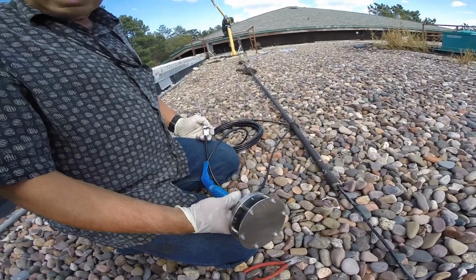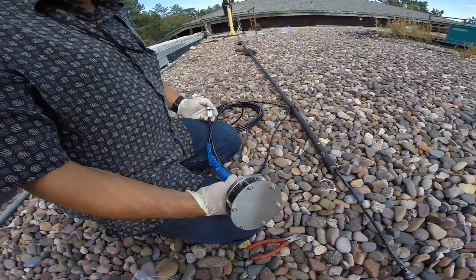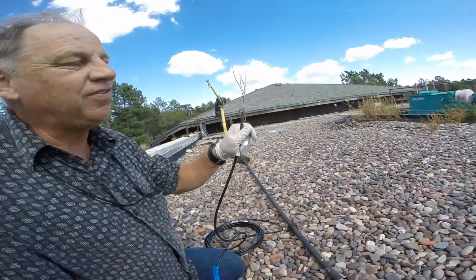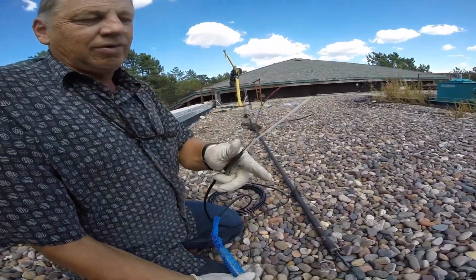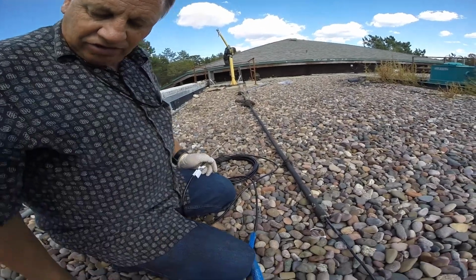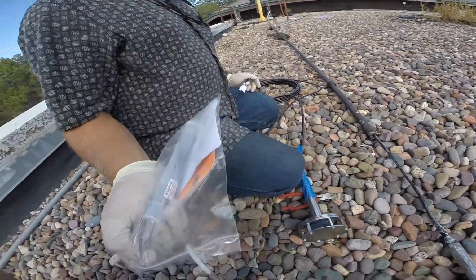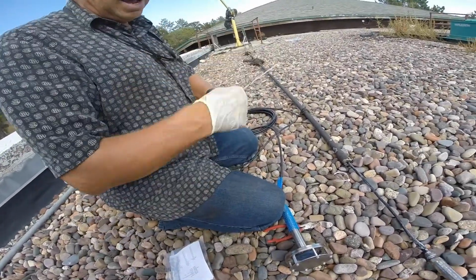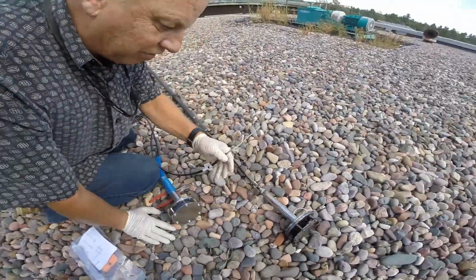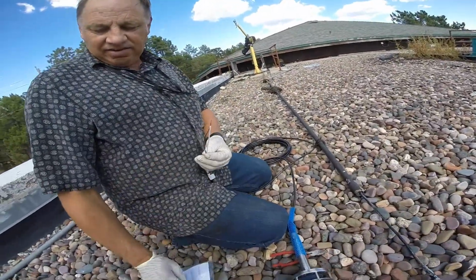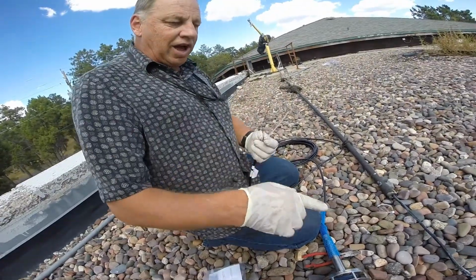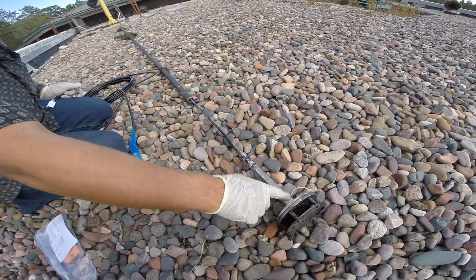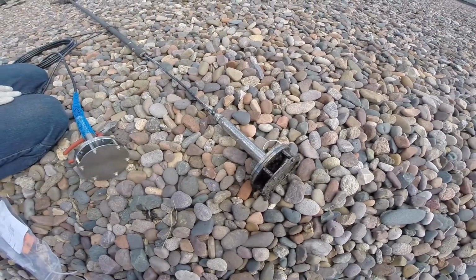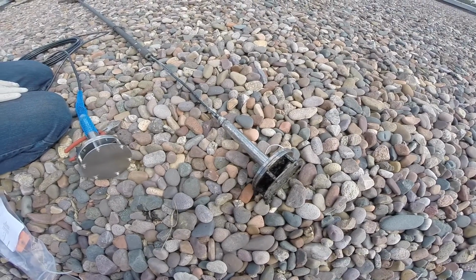So this is how we find out how deep the water is, by measuring the pressure of the water relative to atmospheric pressure. That's why we have this tube, and it's protected with a desiccant to keep moisture from getting back down inside it. The reason this one failed is that the desiccant ultimately failed and moisture got down in here.